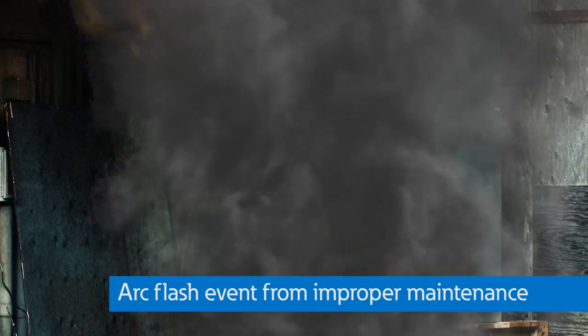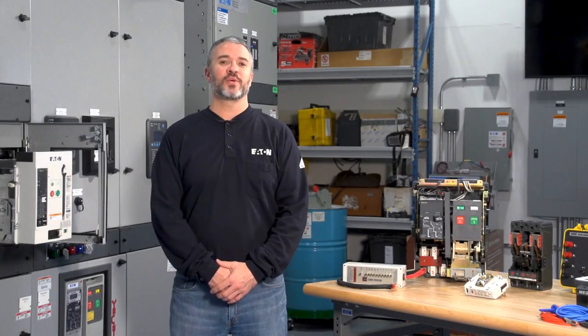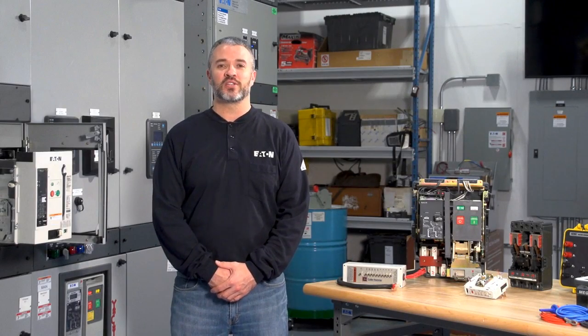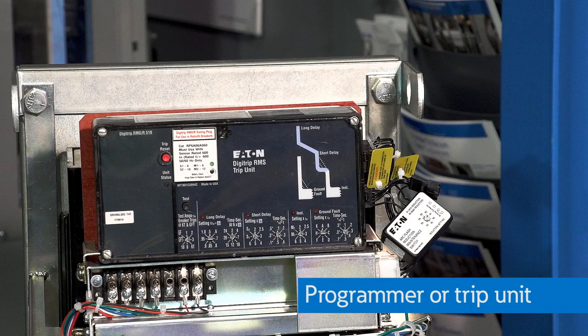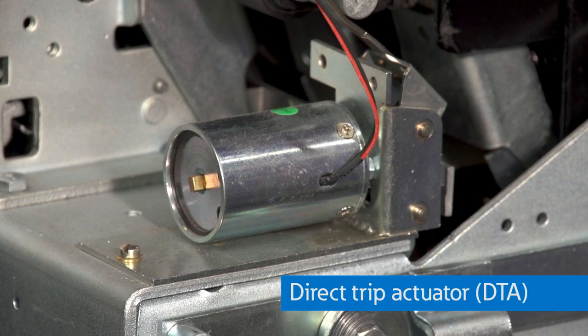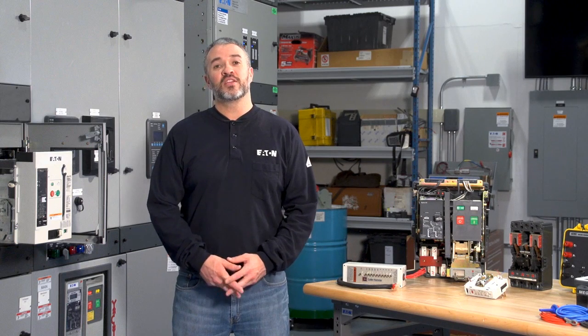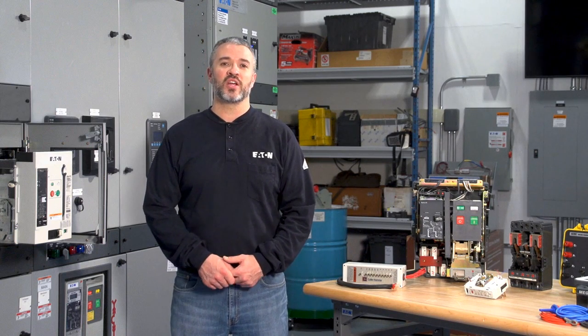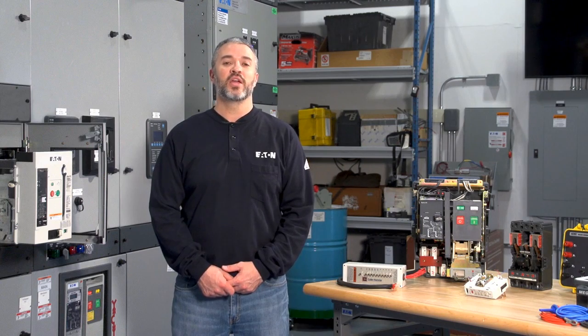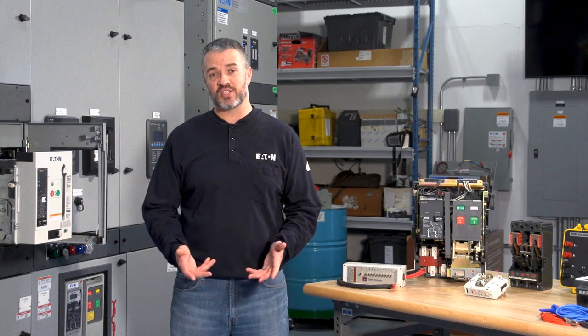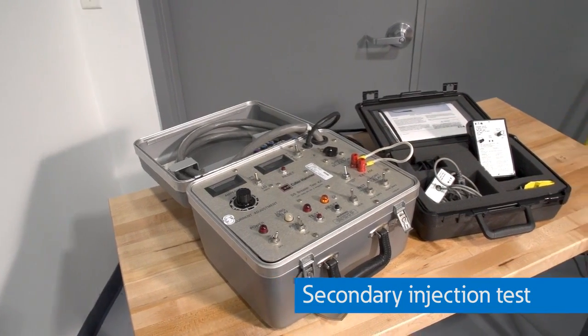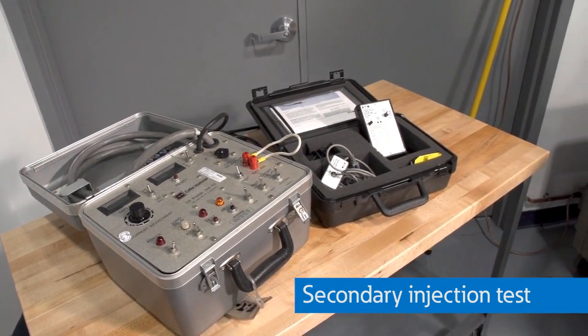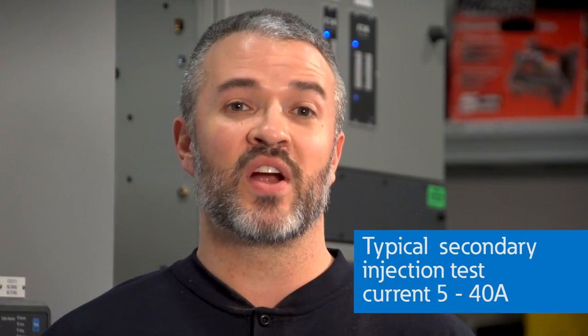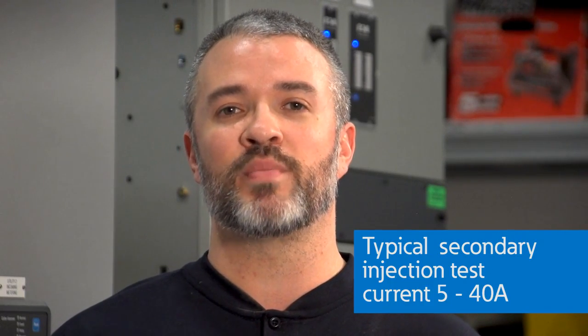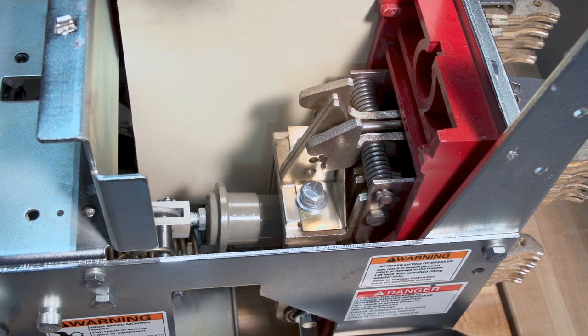The trip system on a circuit breaker is made up of several different components that at least include a programmer or trip unit, current transformers, and direct trip actuator or DTA. The typical methods to test the proper functioning of the protection system on a circuit breaker is by secondary or primary injection testing. A secondary injection test is done by connecting directly to the trip unit and injecting a low amount of current to verify the operation of the trip unit and direct trip actuator, but does not apply any current directly to the circuit breaker's primary contacts.